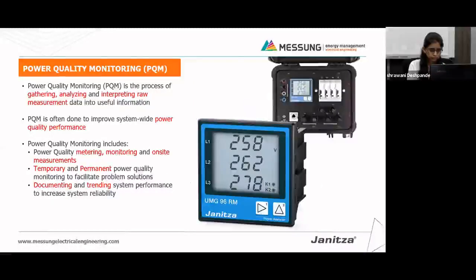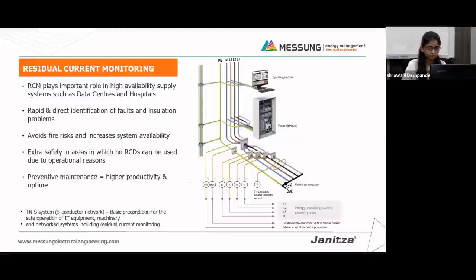Shravani, one minute, go back. I would like to tell the audience today that if you ever hear of an electrical fire, or hear that a building burned down because of electrical short circuiting, it is because of residual current. Had that establishment used RCM meters and gotten an anticipation of the RCM, this could be avoided. Residual current can happen in any part of the factory. It is not necessary that you will measure it at the PCC level; it may happen at a shop level, it may even happen at a machine level, or at a junction box level. This is many times due to faulty wiring, loose connections, sparking in the contacts, and things like that.